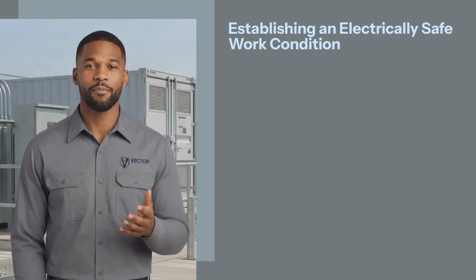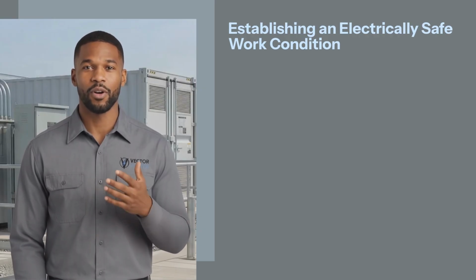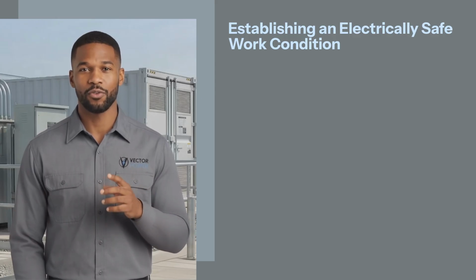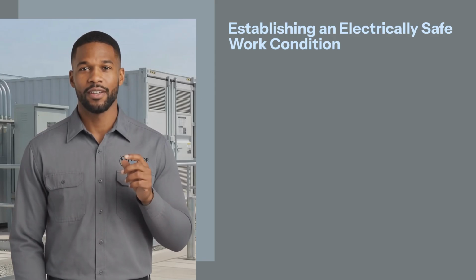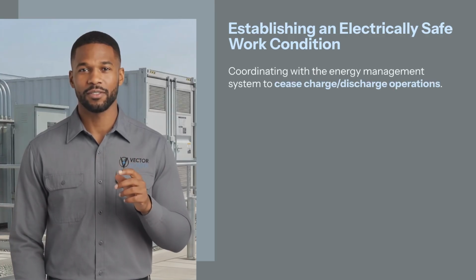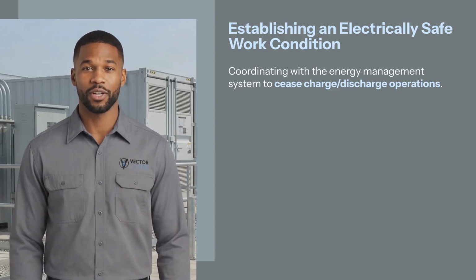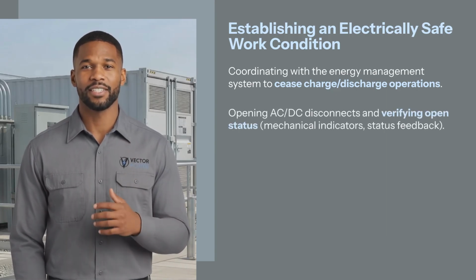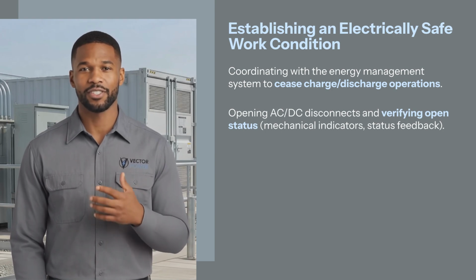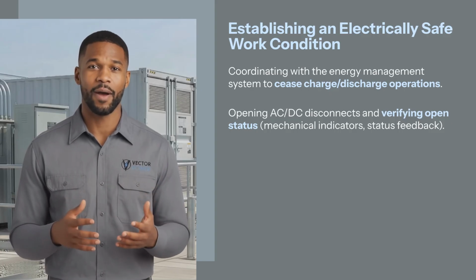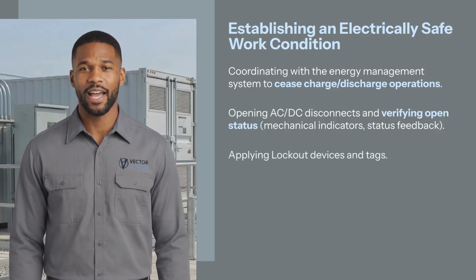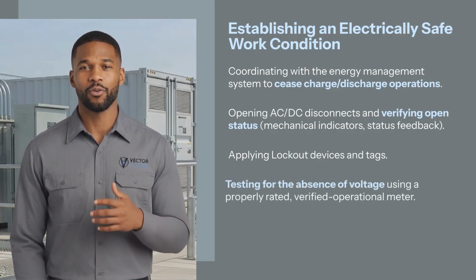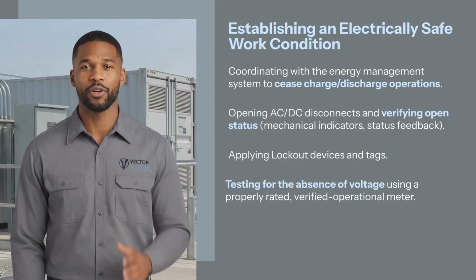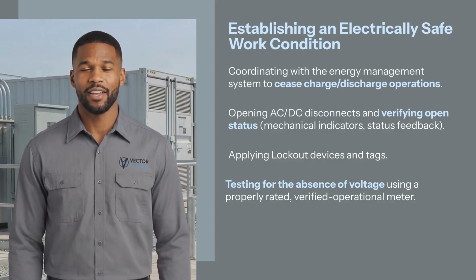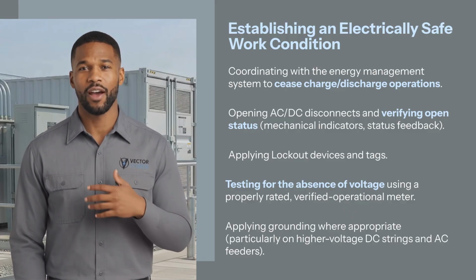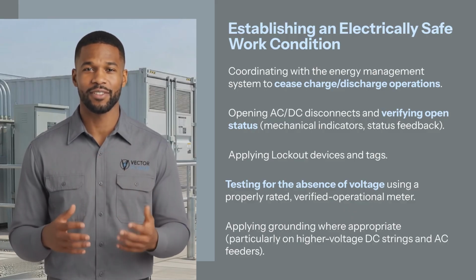Wherever feasible, NFPA 70E requires de-energization before working on electrical equipment. For battery energy storage systems, typical steps will include coordinating with the energy management system to cease charge or discharge operations, opening AC and DC disconnects and verifying their open status, for example, through mechanical indicators or status feedback, applying lockout devices and tags, testing for the absence of voltage using a properly rated and verified operational meter, and finally, applying grounding where appropriate, particularly on higher voltage DC strings and AC feeders.